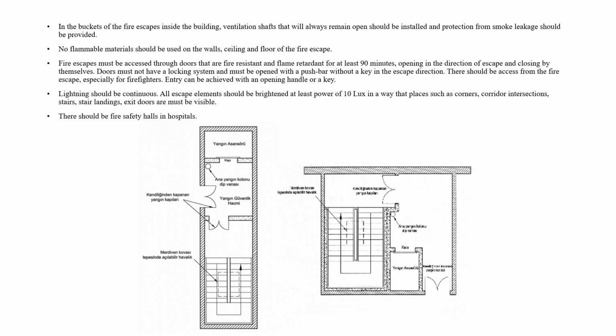No flammable materials should be used on the walls, ceiling and floor of the fire escape. Fire escapes must be accessed through doors that are fire resistant and flame retardant for at least 90 minutes, opening in the direction of escape and closing by themselves. Doors must not have a locking system and must be opened with a push bar without a key in the escape direction. There should be access from the fire escape, especially for firefighters. Entry can be achieved with an opening handle or a key.